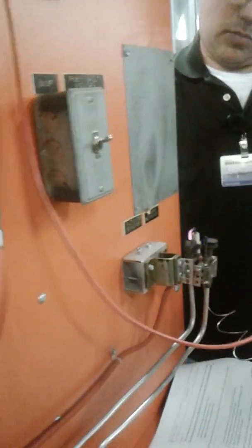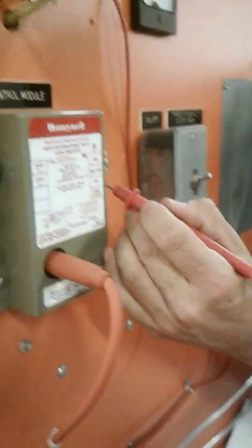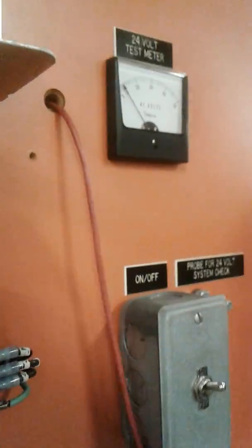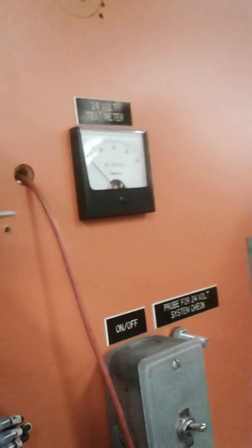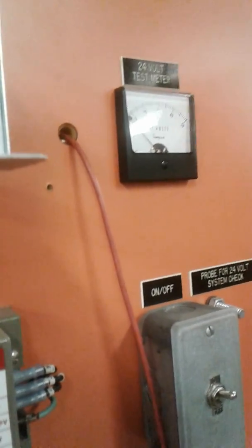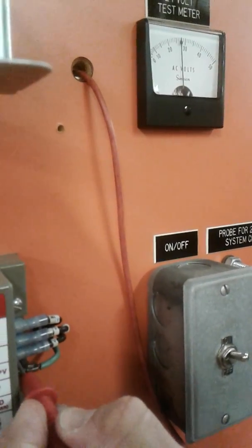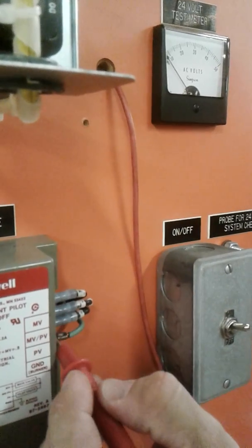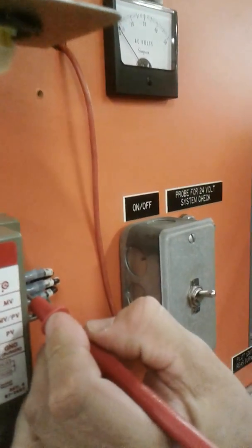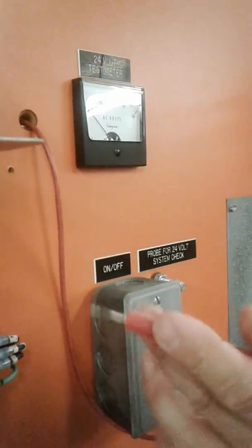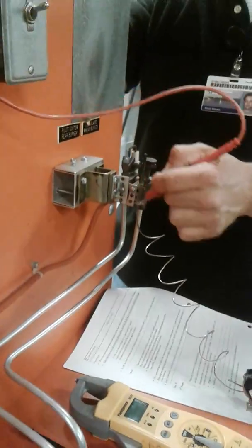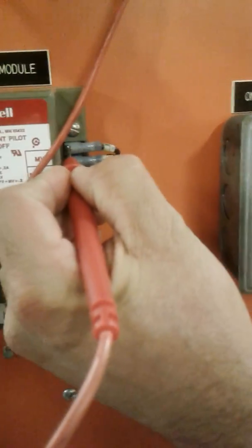Okay, so let's take a look at something. See? We're getting 25 volts to the pilot valve down here. Well, technically, this is supposed to be supplying the voltage down there. See, we're getting voltage to the pilot valve, but we're not getting voltage to the main valve. Why are we not getting voltage to the main valve? Because the pilot valve didn't light yet. We need to have the pilot on first before we get power to the main valve. Once we do that, then we're going to have power to our main valve. And we do. Okay? If you want to use this, you can.